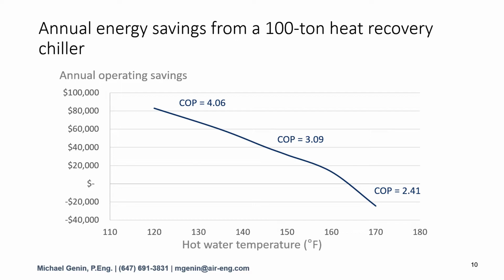Generally, the efficiency of the system decreases with an increase in hot water temperature, and as such, the operational savings diminish. This relationship is mostly linear, with the exception of very high water temperatures, with, in this case, 170 degrees being the upper limit for most chillers. And this limit is a function of refrigerants and the compressors used today. The efficiency tapers off at this high temperature, and in fact the operational savings become negative, which means that the heat recovery system is more costly to operate than a conventional system.